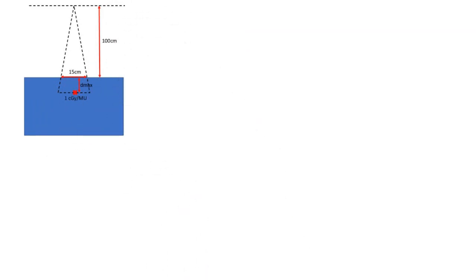Now just as we did with the photon calculations, we can draw out our geometry. So this is our reference condition here. We have our cone size of 15 by 15, SSD of 100 centimeters at a depth of D max. That's where we're delivering one cGy per monitor unit.